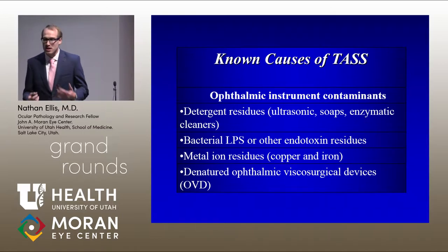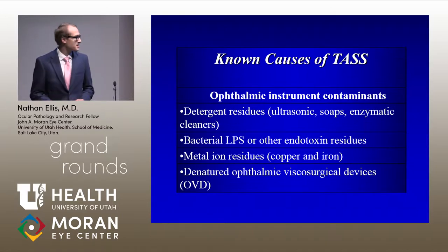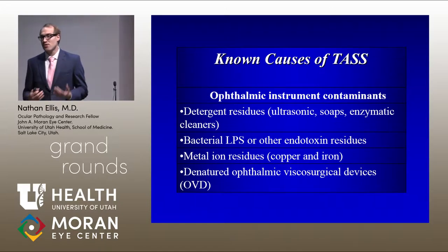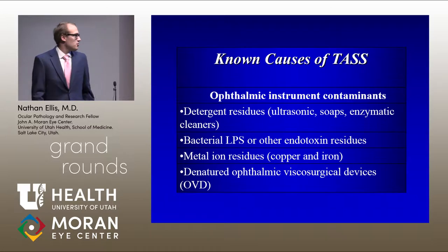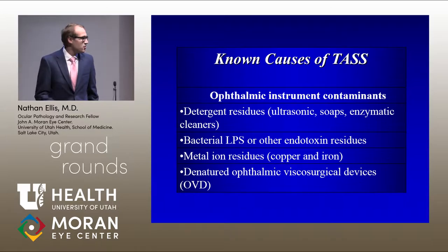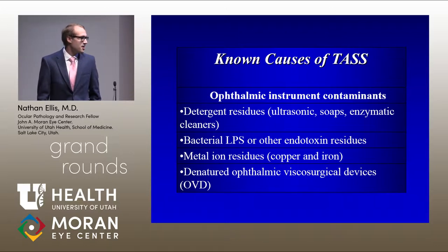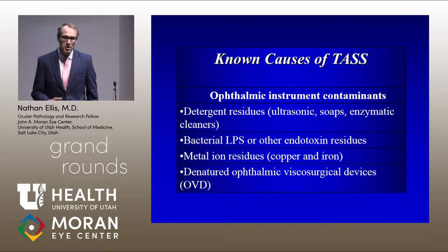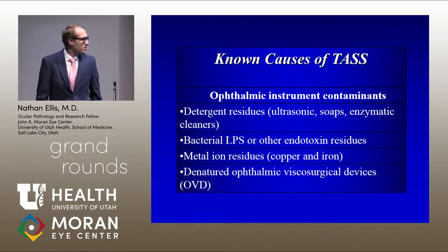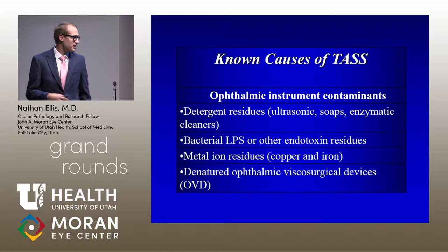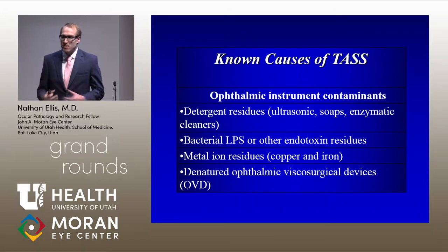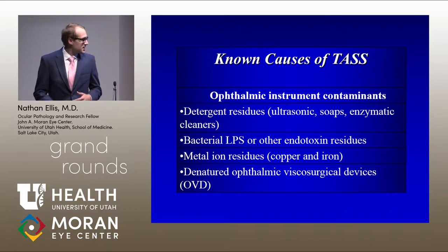One of the most common causes of TASS is ophthalmic instrument contamination through a variety of mechanisms. The most common is detergent residues — from soaps, enzymatic cleaners, or ultrasonic baths, which can harbor gram-negative bacteria. Bacterial lipopolysaccharides and other endotoxins from gram-negative bacteria found in tap water and ultrasonic baths are also implicated. Metal ion residue from copper and iron in older hospital piping was seen in earlier years, as well as denatured ophthalmic viscosurgical devices (OVD).